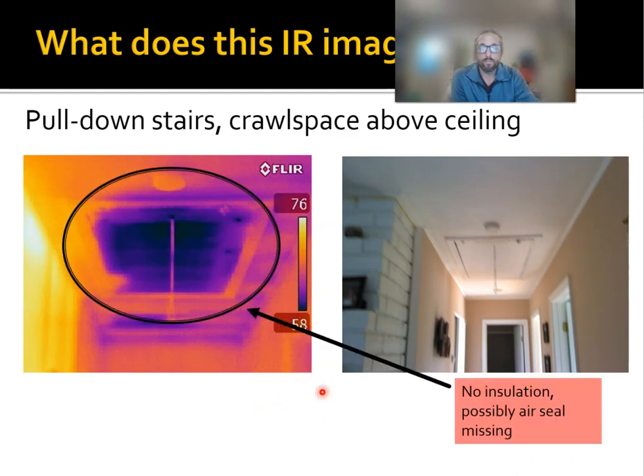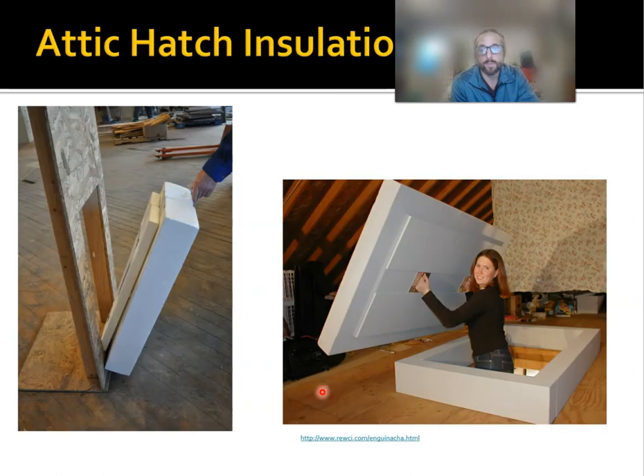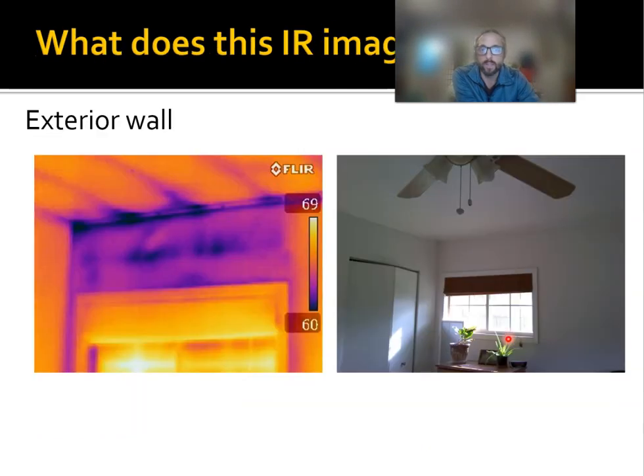Now this is a little trickier. They do make caps for this, like this, right? So it's something you buy in the store. There's something you can build on your own. They make these nylon caps too, but that's not a good insulator. So this is really what you want to do. You need foam. That's great. That looks to me to be EPS, so it looks like it's just Styrofoam. But yeah, probably like 3 inches of that. So that's pretty solid, like R15 or so, maybe R16. So yeah, you want to cap that off. You want to find a way to insulate that.